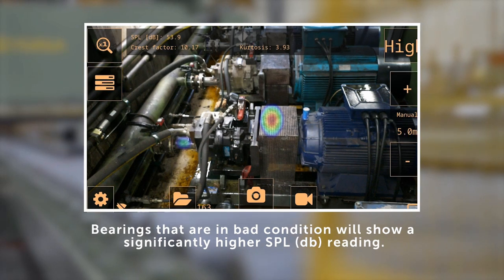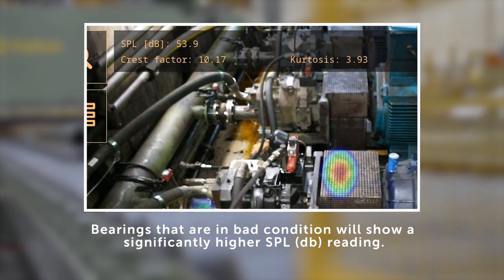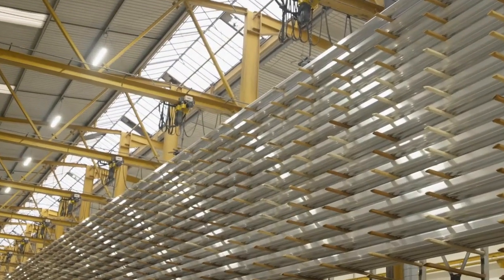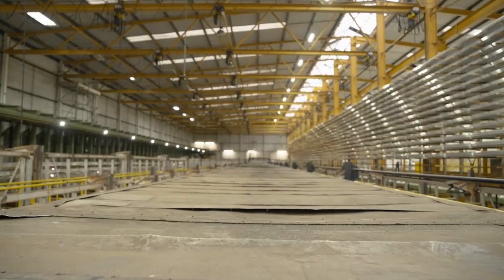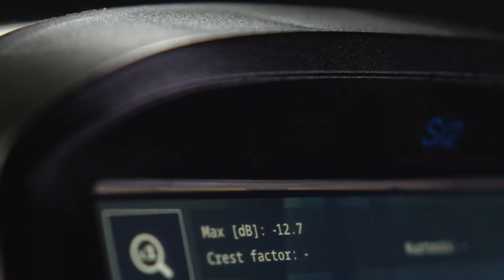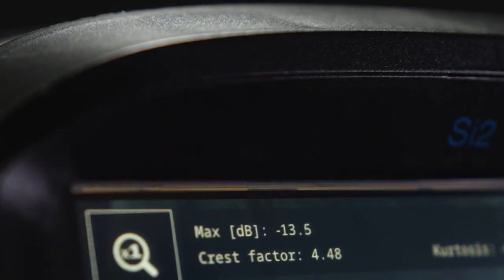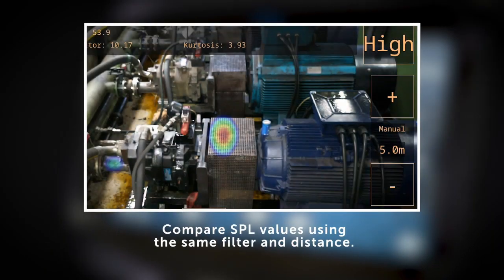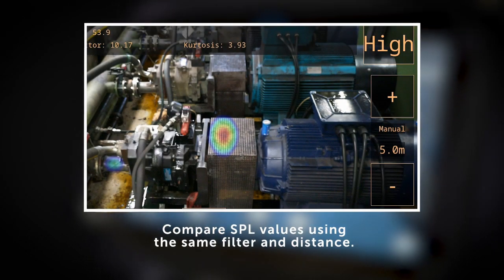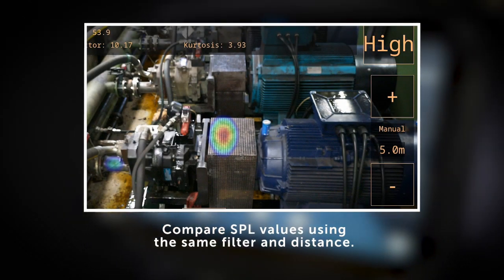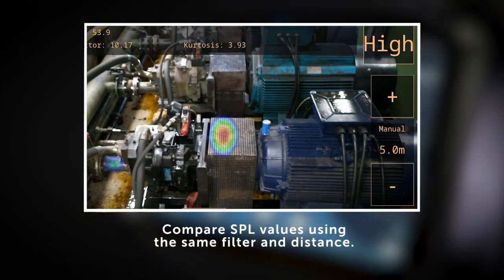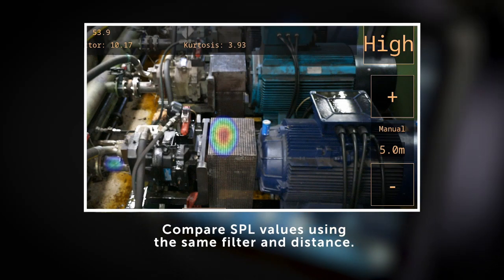The bearings that are in bad condition will show a significantly higher SPL reading than bearings that are in good condition. As the condition gets worse, the SPL reading is likely to increase further. The comparison should be done using the same filter and distance; otherwise, the SPL values cannot be directly compared.